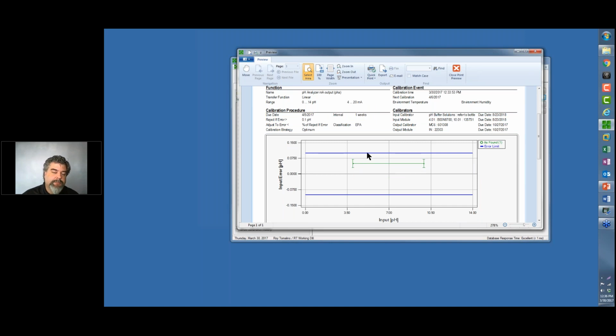So here we see our dots. The blue lines represent tolerance, and these guide bands that you're seeing are the uncertainty of my standard. On my pH bottles, it said that it was plus or minus 0.02 pH, that it was accurate to within 0.02. So I put that into my standard, and what you're seeing is a visual representation of that 0.02. If I'm at 4, it could be anywhere from 3.98 up to 4.02. And that's what those bars mean. So that's uncertainty from a visual perspective.